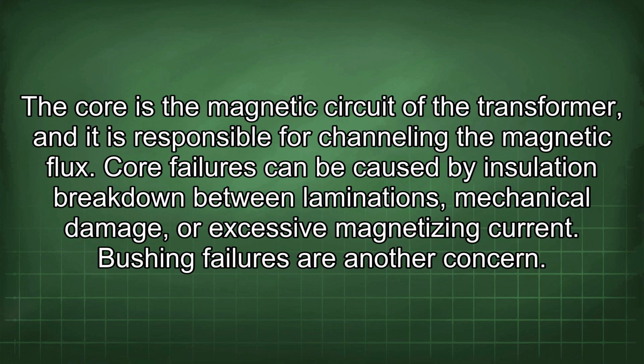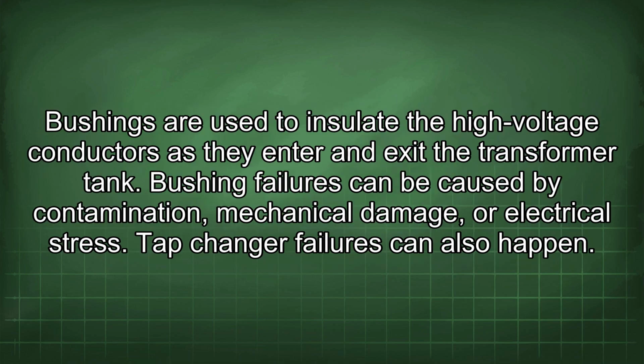Bushing failures are another concern. Bushings are used to insulate the high-voltage conductors as they enter and exit the transformer tank. Bushing failures can be caused by contamination, mechanical damage, or electrical stress.